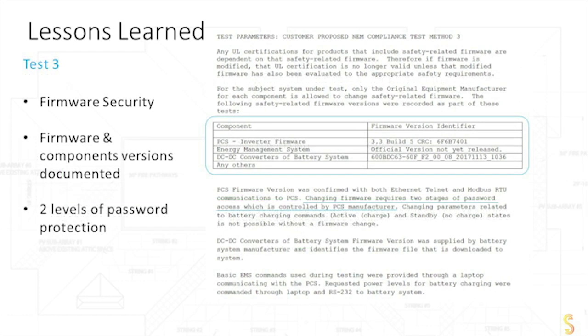This next test, we want to just check that the firmware can be recorded by the inverter manufacturer. So, if an inverter manufacturer makes this non-import functionality into the firmware of their inverter, we want to be able to check the version of that firmware, that version number, and be able to cross-correlate it with the manufacturer's part number or the SKU number. And we just want to make sure that model of that inverter has this version of that firmware, and if so, the inverter does what we think it's going to do. Pretty simple. It's basically just checking a specification. And this specification, of course, can be checked by UL and stamped appropriately or approved.